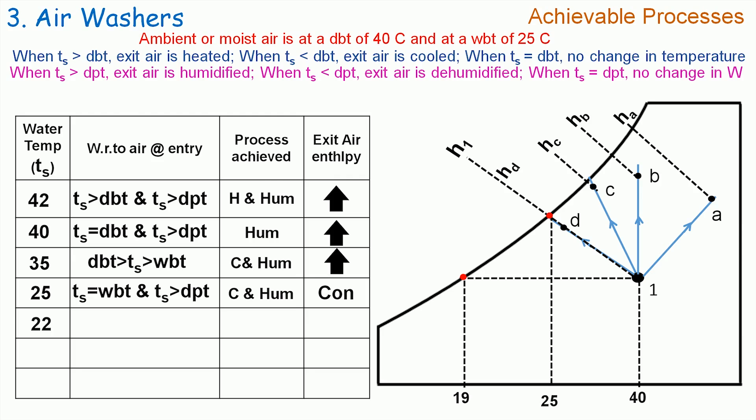Let us now supply the spray water at 22°C. Here TS is less than the dry bulb temperature, hence air is cooled. And TS is greater than the dew point temperature, hence air is humidified. Therefore, the achievable process by the air washer is cooling and humidification. But please note that the spray water temperature TS is less than wet bulb temperature here. If you plot it on the psychrometric chart, then process 1E will be representing it. The enthalpy HE is less than H1, hence exit air enthalpy decreases in this case.